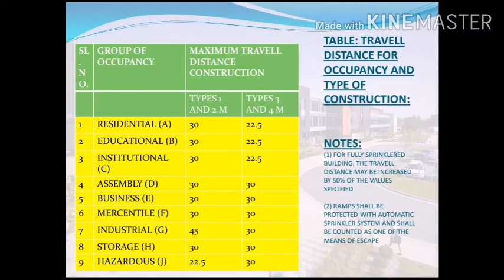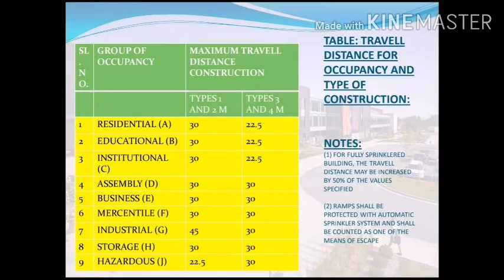As noted below the table: for a fully sprinklered building, the travel distance may be increased by 50 percent of the specified values, provided there is a proper arrangement of fire-related systems such as a fire alarm, firewall, or sprinkler. Ramps shall be protected with an automatic sprinkler system and shall be counted as one of the means of escape. That covers the content on travel distance. The next slide will discuss horizontal exits.